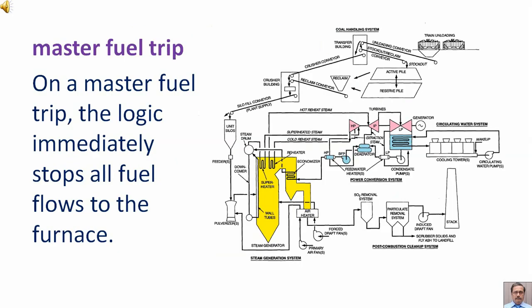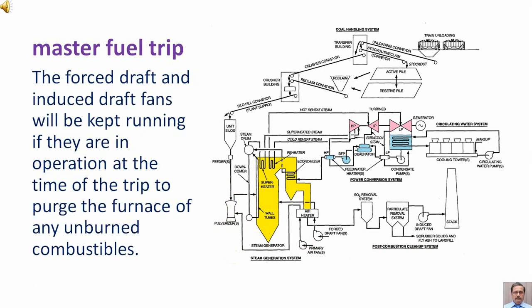On a Master Fuel Trip, the logic immediately stops all fuel flows to the furnace. Here we have the pulverizer which is giving fuel flow to the furnace. The forced draft and induced draft fans will be kept running if they are in operation at the time of the trip, to purge the furnace of any unburned combustibles.